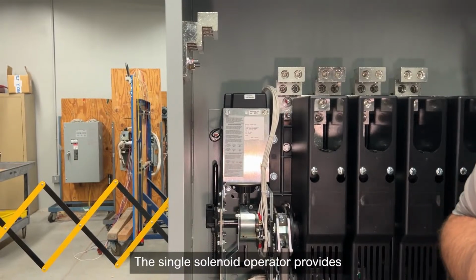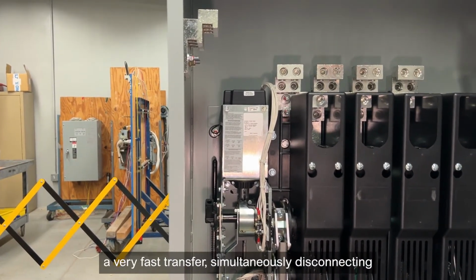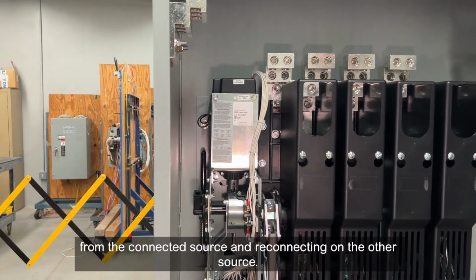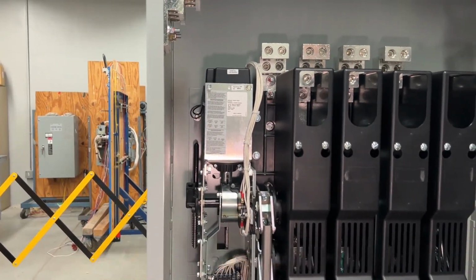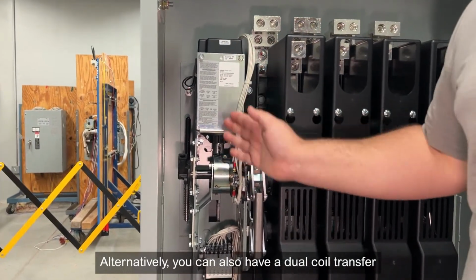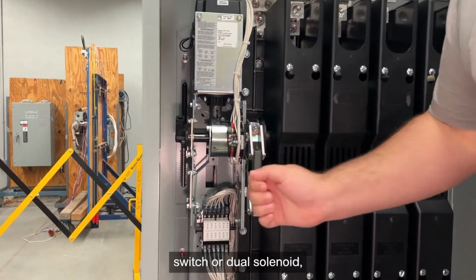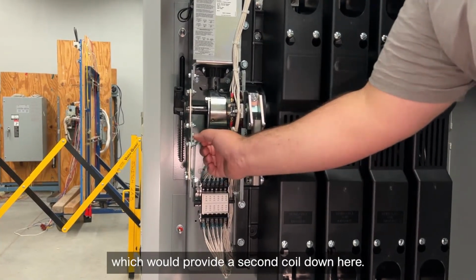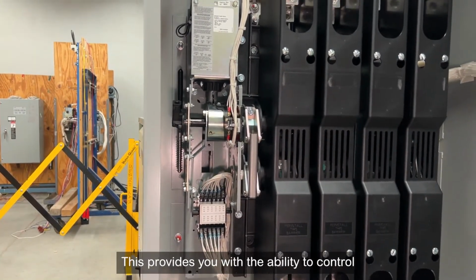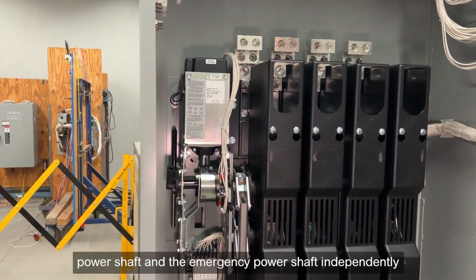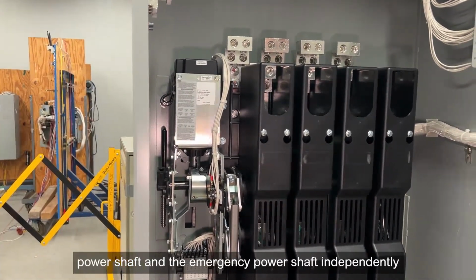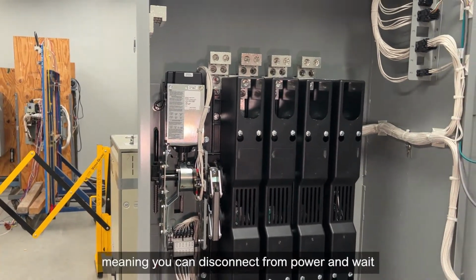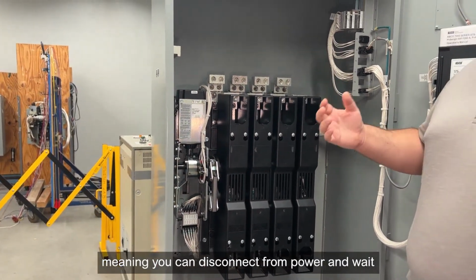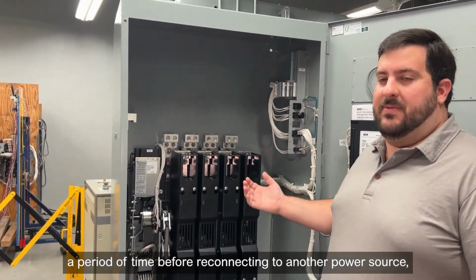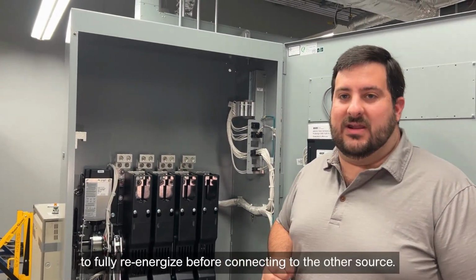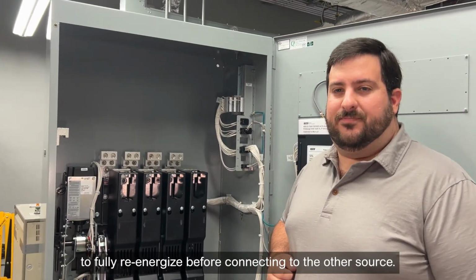The single solenoid operator provides a very fast transfer, simultaneously disconnecting from the connected source and reconnecting on the other source. Alternatively, you can also have a dual coil transfer switch or dual solenoid, which would provide a second coil down here. This provides you with the ability to control the normal power shaft and the emergency power shaft independently and control those contacts independently, meaning you can disconnect from power and wait a period of time before reconnecting to another power source, allowing your loads to fully de-energize before connecting to that other source.